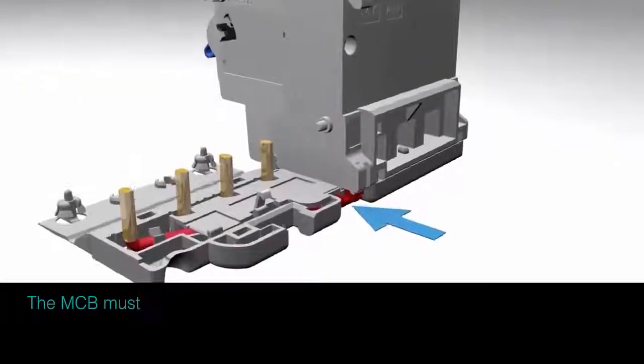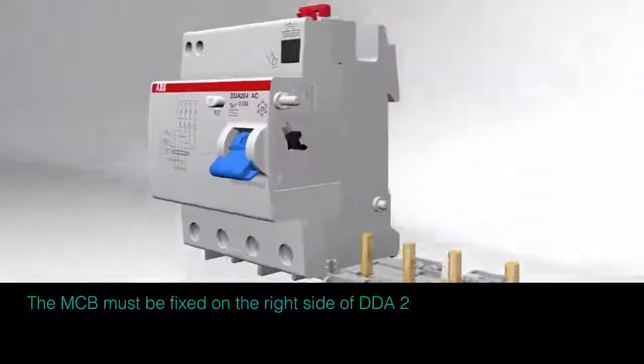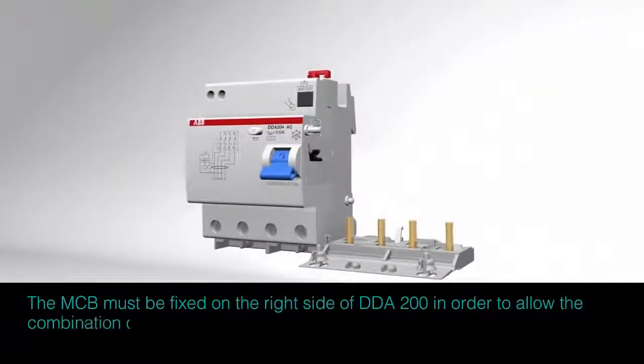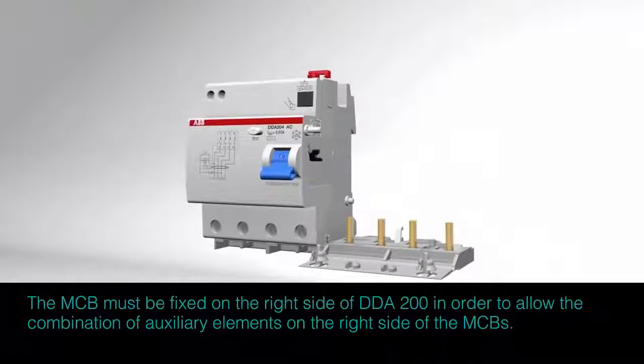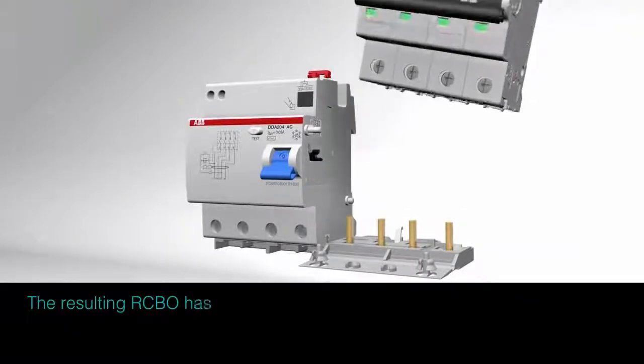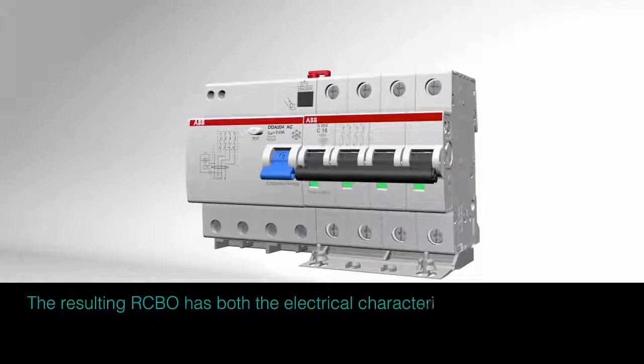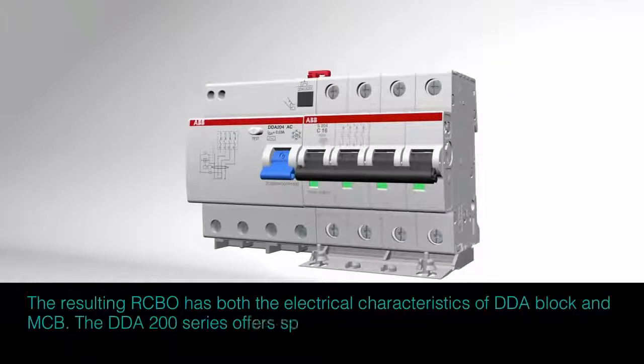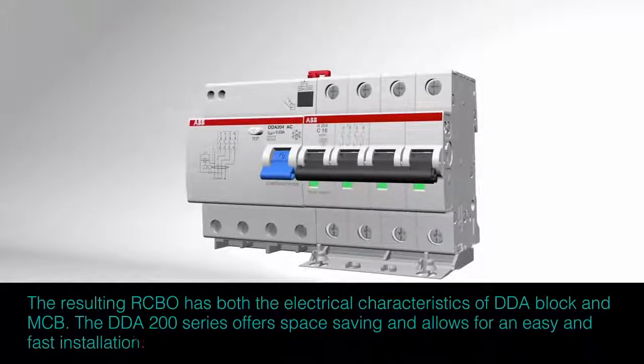The MCB must be fixed on the right side of the DDA 200 in order to allow the combination of auxiliary elements on the right side of the MCBs. The resulting RCBO has both the electrical characteristics of DDA block and MCB. The DDA 200 series offers space saving and allows for an easy and fast installation.